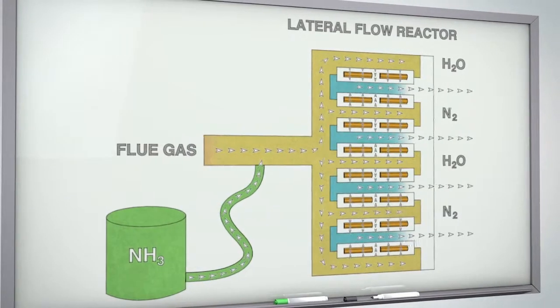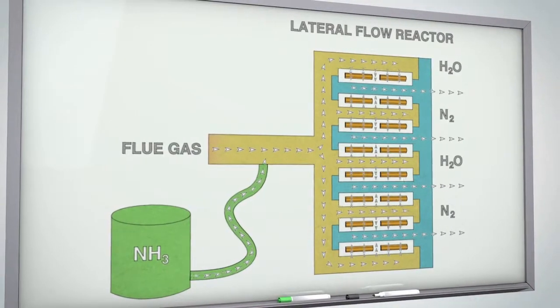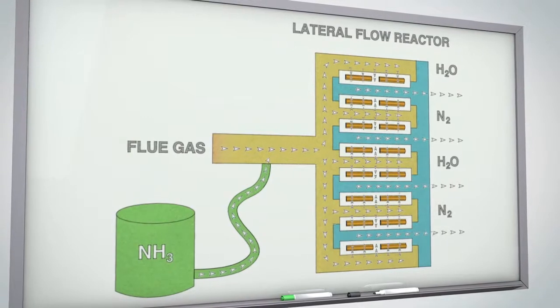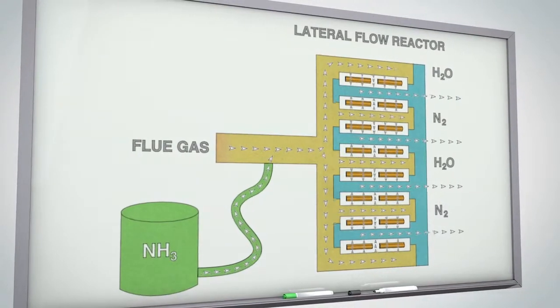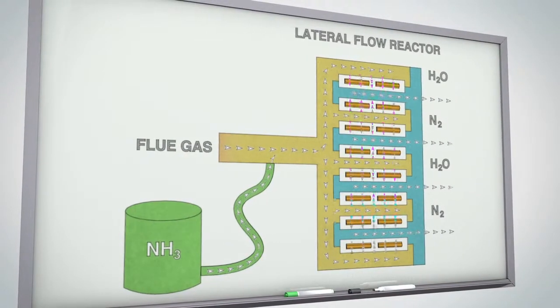The NOx and ammonia react in the presence of the catalyst, converting the nitrogen oxides to naturally occurring nitrogen and water, reducing as much as 99% of NOx emissions.